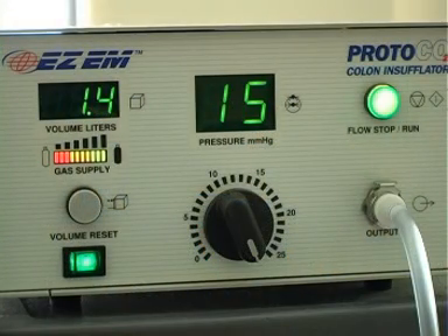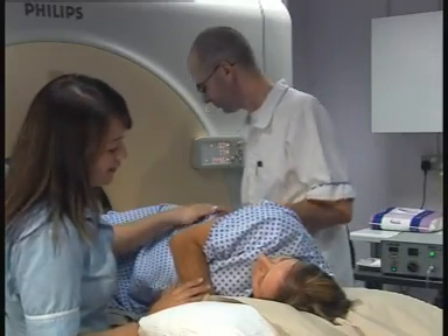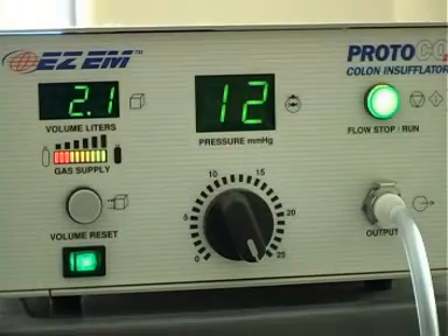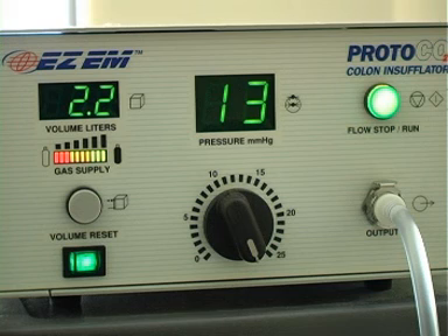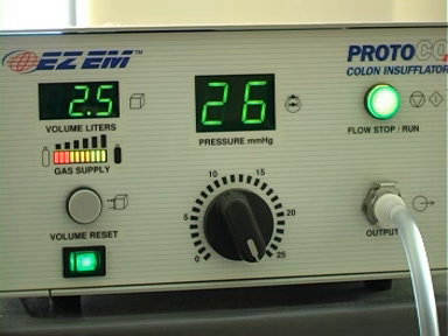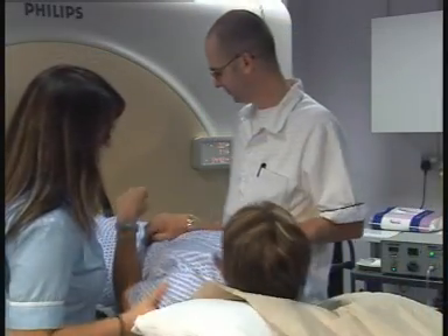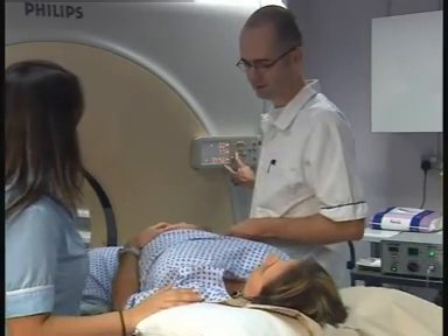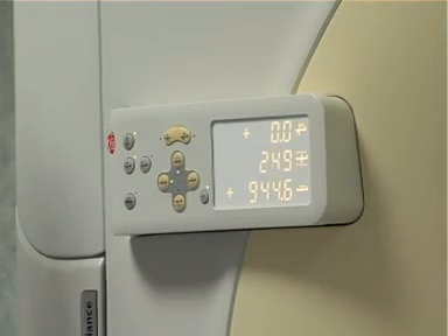After approximately 1.5 liters of carbon dioxide have been introduced, the patient is repositioned so they are supine. Insufflation continues until approximately 2 to 3 liters of gas have been insufflated, by which time the colon is usually full. When full, we often recognize the pressure within the rectum builds and exceeds 25 millimeters of mercury. This pressure, which is measured at the rectal catheter, is displayed on the front of the device. A safety cutout mechanism will stop further insufflation until the rectal pressure drops below 25 millimeters of mercury. This point often represents where the colon is full and the ileocecal valve remains competent.